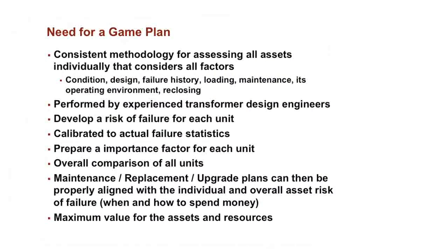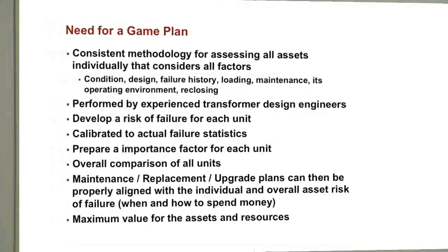So doing a fleet assessment, we see that as giving you a game plan, giving you something that you can go forth and then use your capital and your resources to the best. So what it is, it's a consistent technical methodology for looking at all the transformers and individually calculating the risk of failure of each one of them and then overall a risk of failure. And the things that it takes into account are the condition of the transformer, all the design features of the transformer, and also the design features compared to the sister units that are known. The loading, the maintenance, the operating environment, and the reclosing practice.